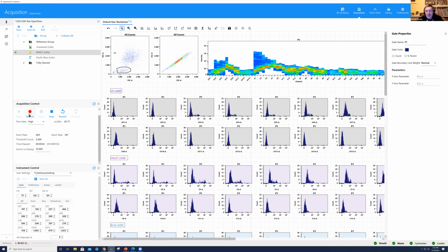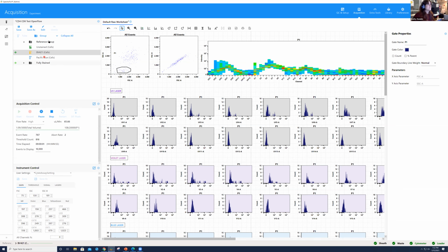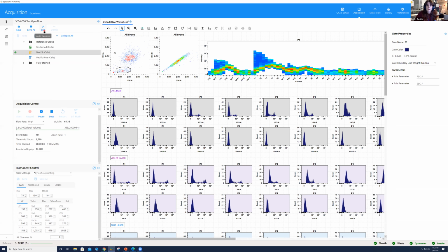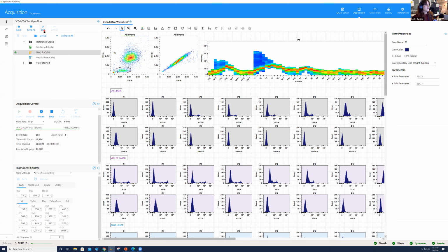Do you set, as another question, sorry, Kathy, do you set a volume to aspirate when you start this? That is in the initial settings. So if we went back to edit and we were looking at the original experimental setup, you do have the option to stop at a certain volume or a certain time. I have about 300 microliters in here. So I could have theoretically said I want to stop at, maybe 150, give myself a little bit of extra volume just in case. I prefer to use that when I'm working with plate mode. If there's a certain volume I want to work with, I don't typically tend to do the volume stopping for tube, but that's personal preference, but you absolutely can.